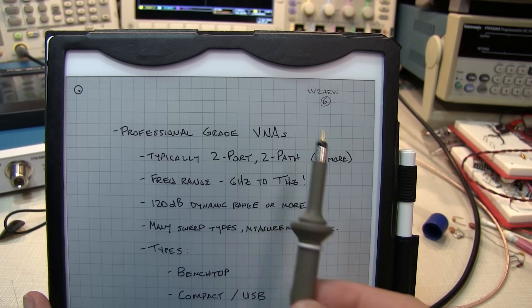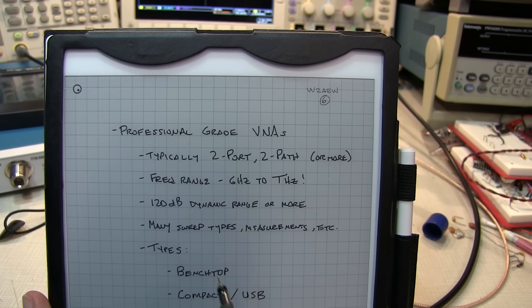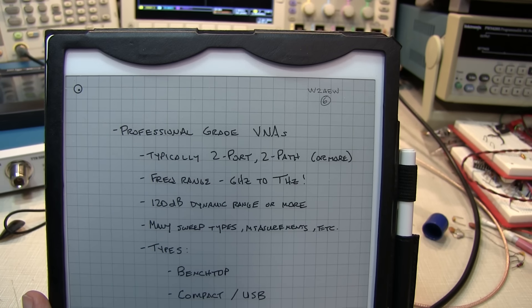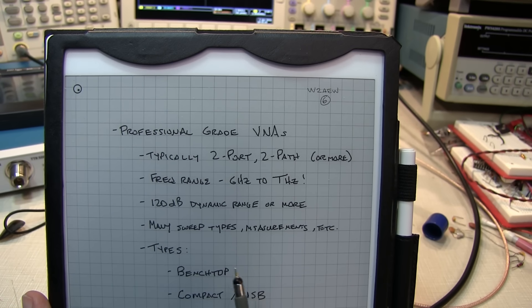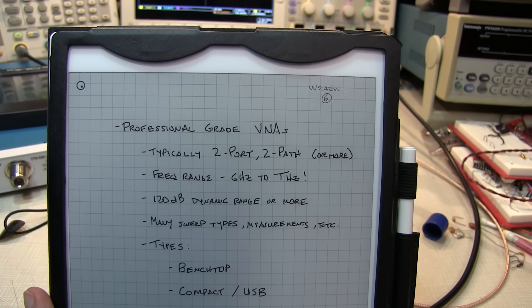The most expensive devices are typically standalone benchtop instruments with two or more ports. But for the more budget-conscious, there are also compact or USB-driven VNAs that have performance coming close to the benchtop instruments, sometimes equaling them, but typically at a lower cost because all the processing and display is handled by an external PC rather than being built into the instrument itself.